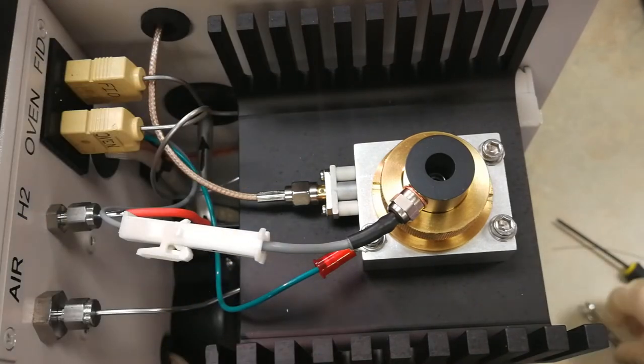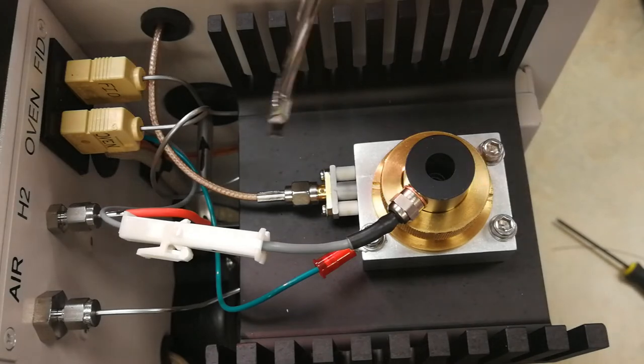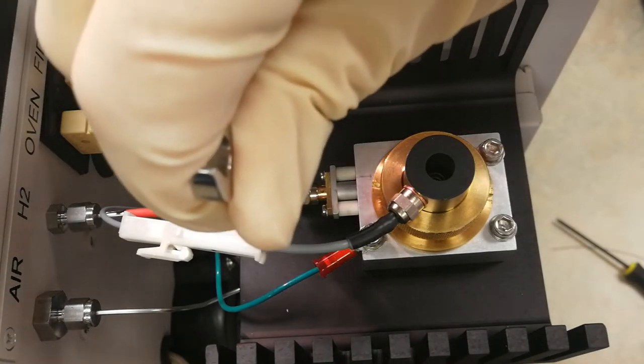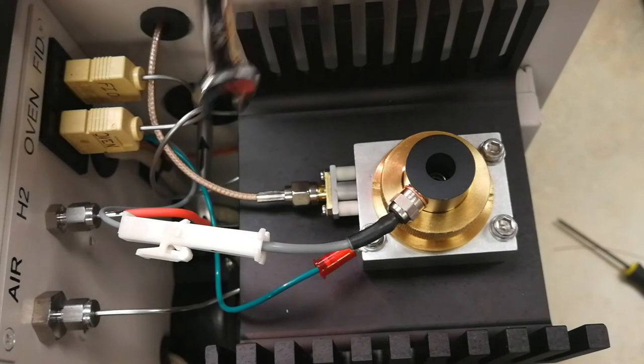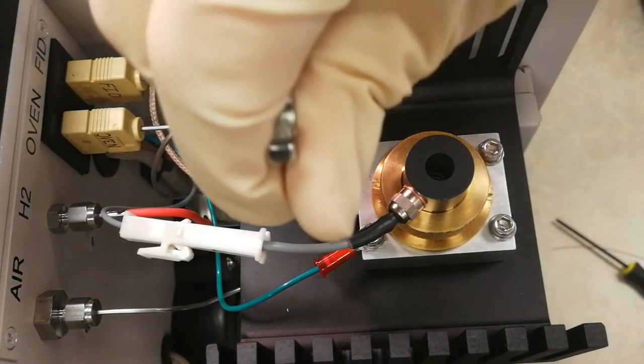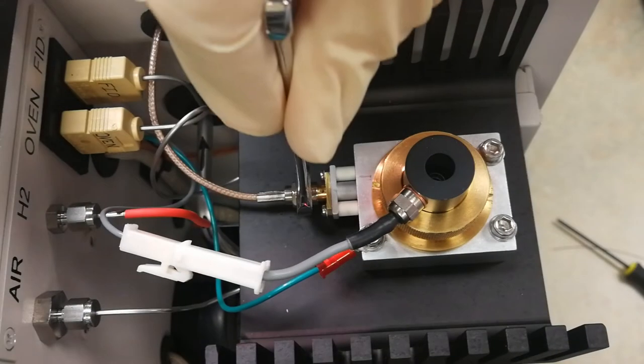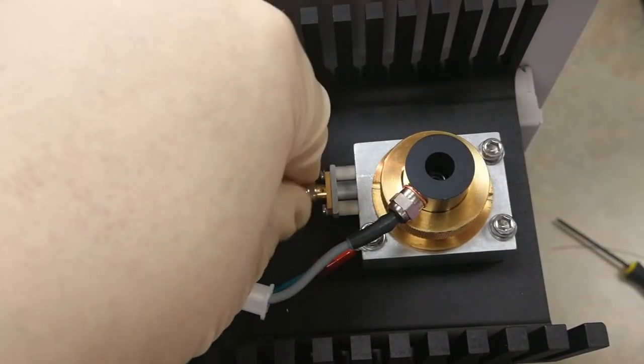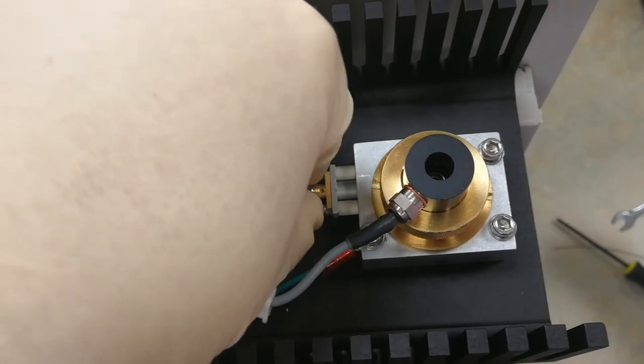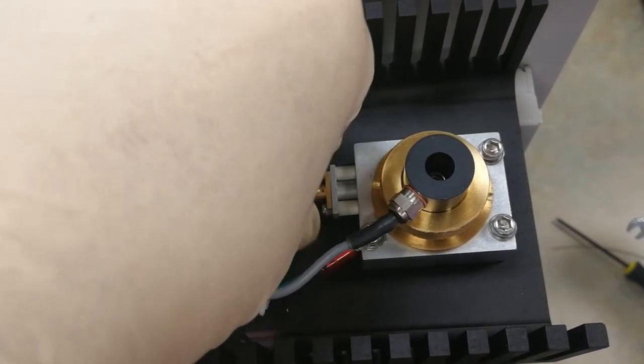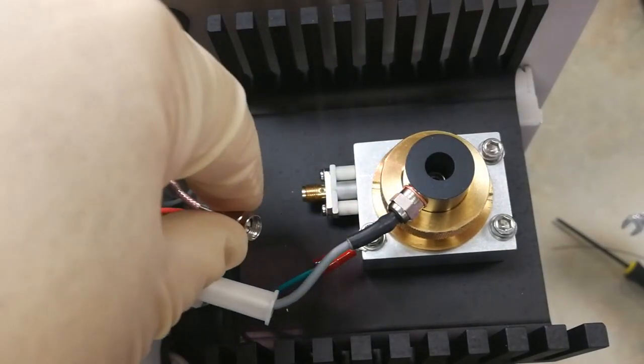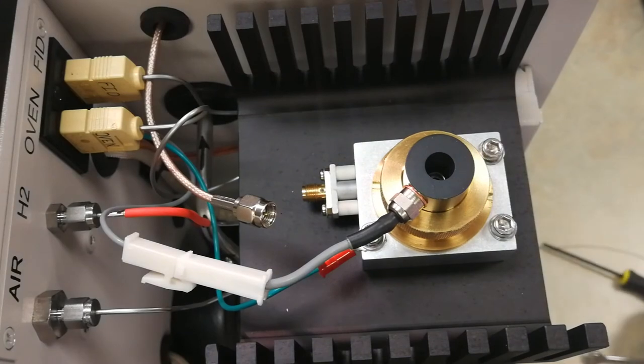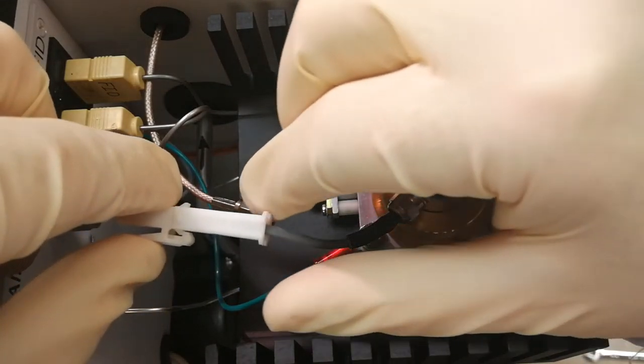You can start with taking your 5/16 wrench and loosening your FID signal cable. You can just push it aside. Disconnect your igniter cable.